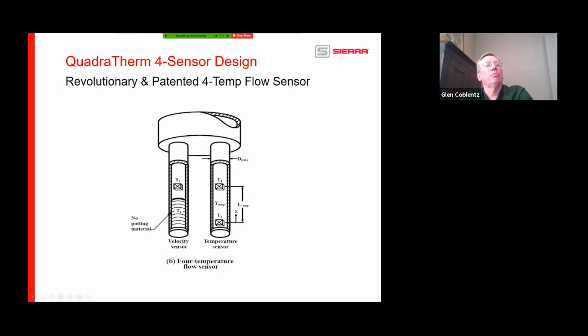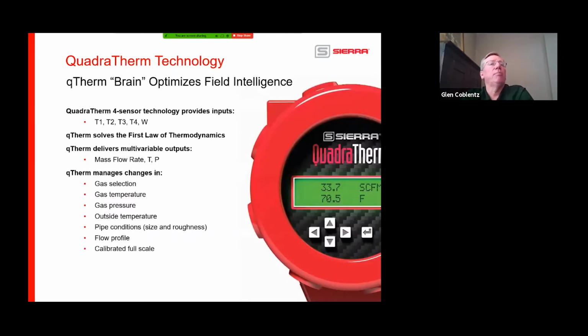But if you look at the Quadratherm, we have 4 temperature sensors. On the velocity sensors, you have one here, here, and then over here. So what we're looking for is heat transfer into the probe. You need to keep track of that, and the Quadratherm keeps track of that. That information goes up to the brain. That's considered false flow, so that is taken out of the equation so that it does not end up being false flow on the reading.